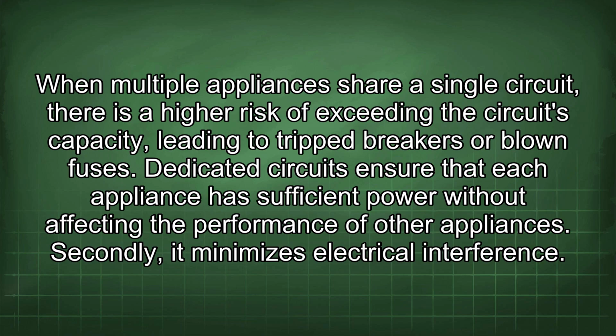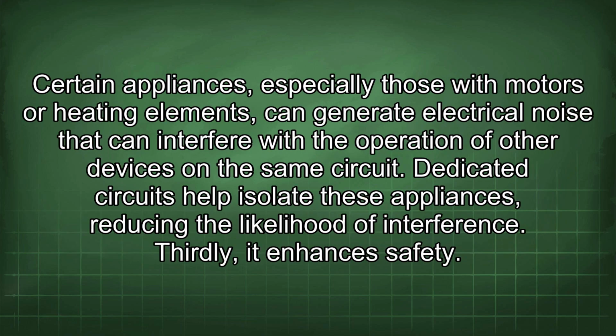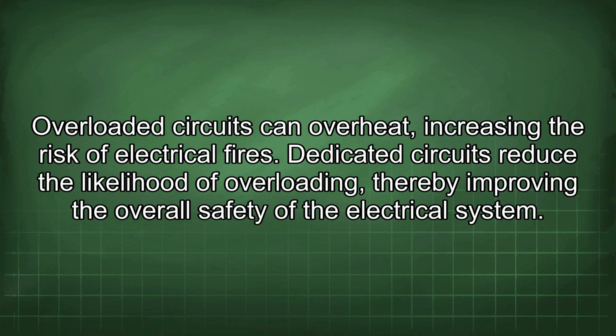Secondly, it minimizes electrical interference. Certain appliances, especially those with motors or heating elements, can generate electrical noise that can interfere with the operation of other devices on the same circuit. Dedicated circuits help isolate these appliances, reducing the likelihood of interference. Thirdly, it enhances safety. Overloaded circuits can overheat, increasing the risk of electrical fires. Dedicated circuits reduce the likelihood of overloading, thereby improving the overall safety of the electrical system.